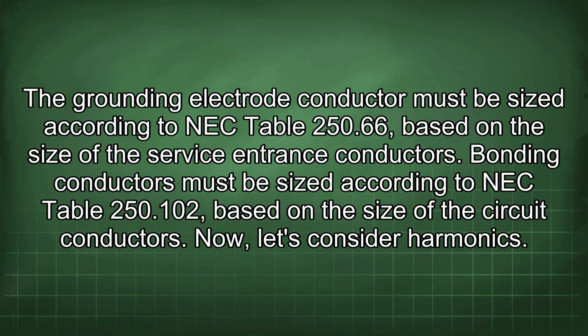The grounding electrode conductor must be sized according to NEC Table 250.66, based on the size of the service entrance conductors. Bonding conductors must be sized according to NEC Table 250.102, based on the size of the circuit conductors.